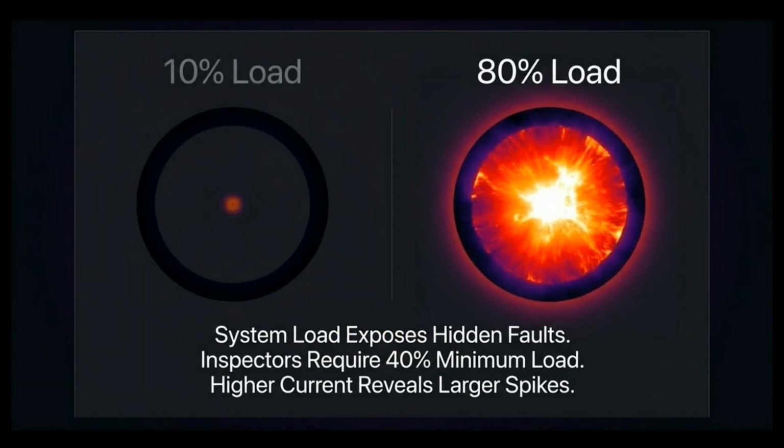System load is crucial. A low-load circuit may not reveal a fault. Inspectors must aim for a minimum of 40% load to expose problems, as higher current reveals larger temperature spikes.